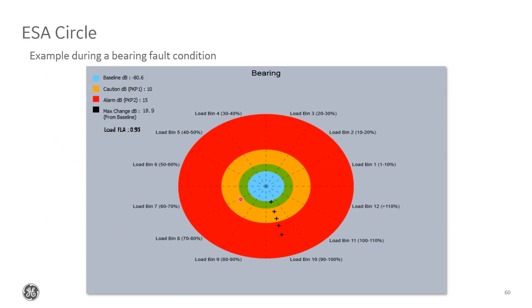At the end of the green point, this would be your first pickup level. So if we have our first pickup level set to a change value of 10, then it would be the baseline plus 10. So this would be 90 decibels here. The outside of the orange area is the second pickup. So it would be your baseline plus the first pickup plus the second pickup. So 80 plus 10 plus 15 would be this area here. And then after here, kind of a moot point. After here, you're basically, you know, in trouble. The time isn't accounted for on here. Basically, you need to have this value rise above the pickup level for the set period of time. And if it stays consistent for that set period of time, then we'll alarm.